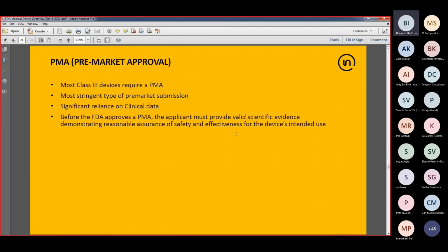The next type of submission is pre-market approval. And as I mentioned earlier, most Class 3 devices will require pre-market approval. This is the most stringent type of pre-market submission, almost always requires clinical data. And before a PMA is approved, the applicant will need to provide valid scientific evidence demonstrating adequate data to support the intended use. So you are not looking at predicate device comparison in a PMA. A pre-market approval is solely for the product itself. Think about implants and other high-risk devices.